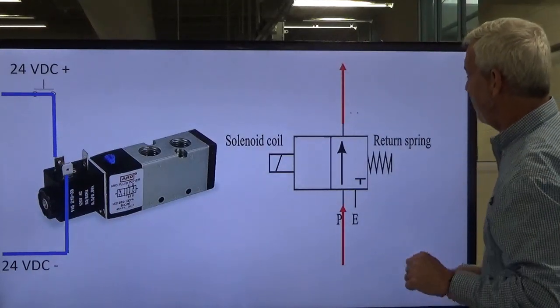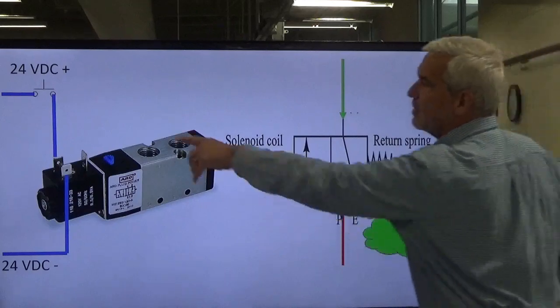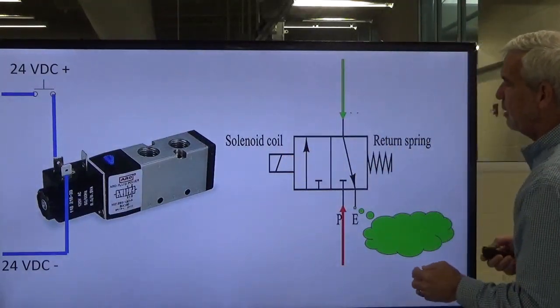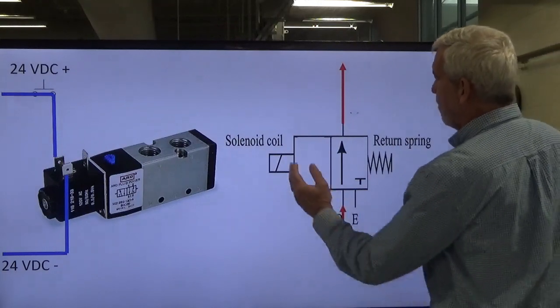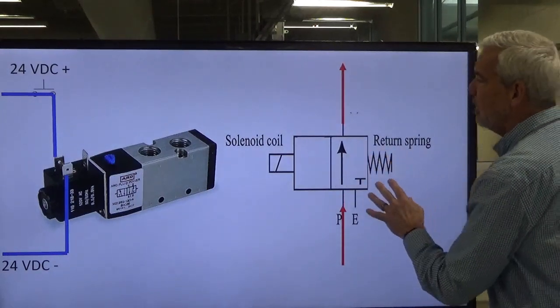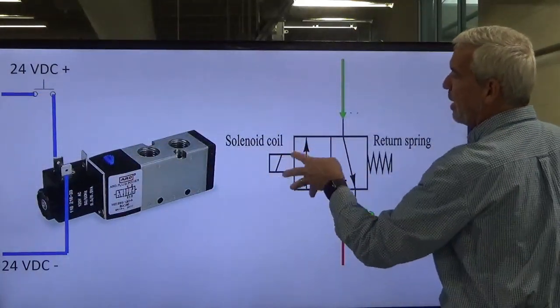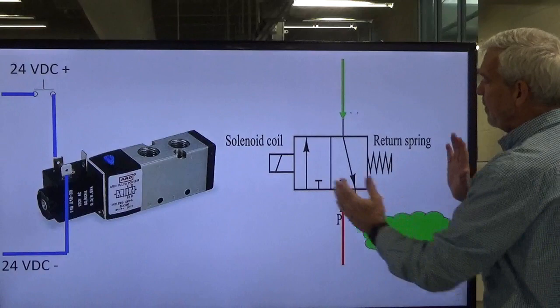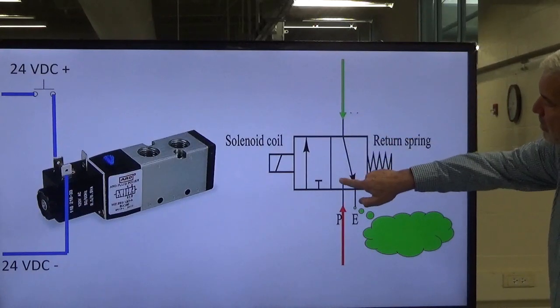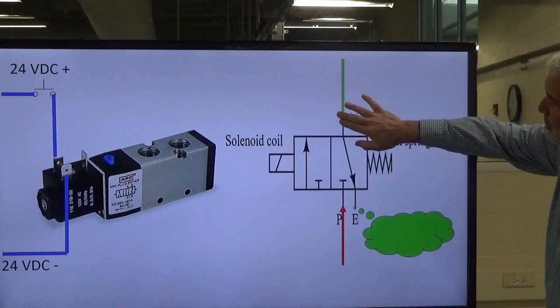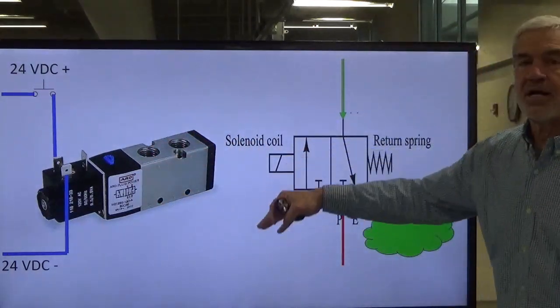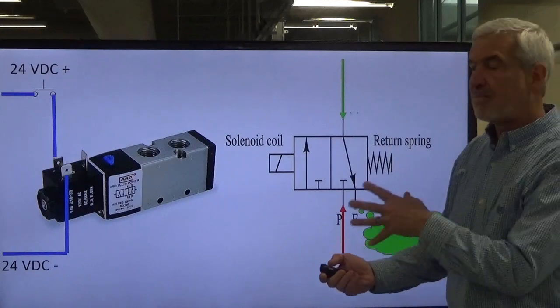When we de-energize, I've let my button off, we no longer have a magnetic field. The spring pressure is now dominant. When we do energize, the magnetic field is stronger than the spring. However, when we take our finger off the button, spring pressure is the dominant pressure. It shoves it back, we've blocked off the system air. Now anything captured in our system goes to exhaust and is exhausted out into the atmosphere. That's the difference between hand-operated and solenoid-operated shutoff valves.